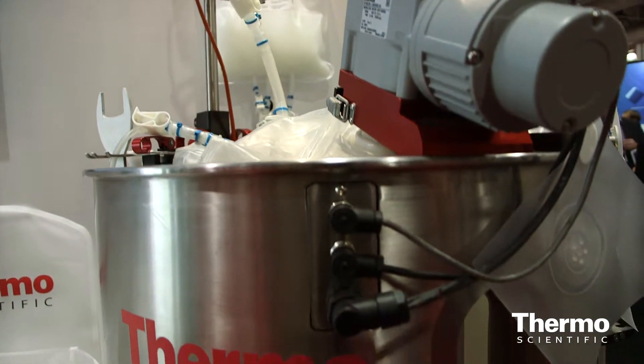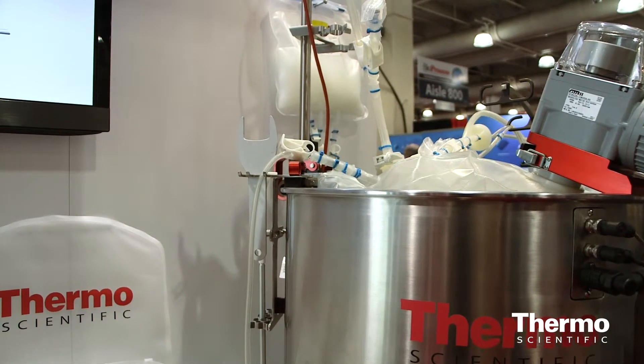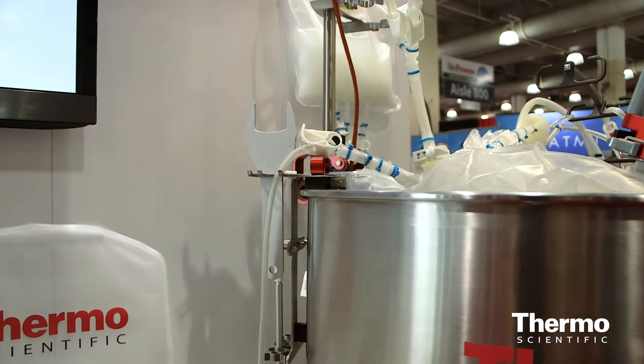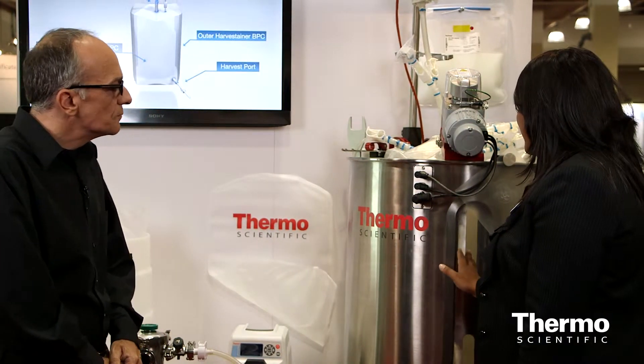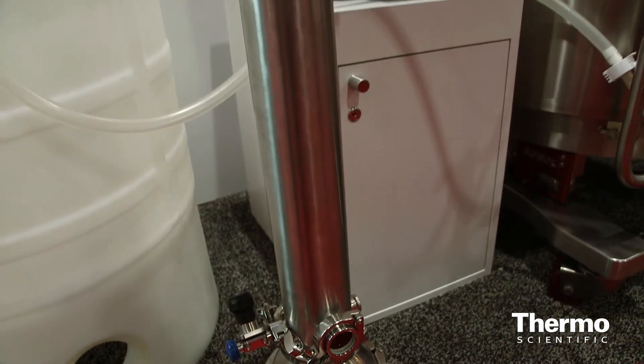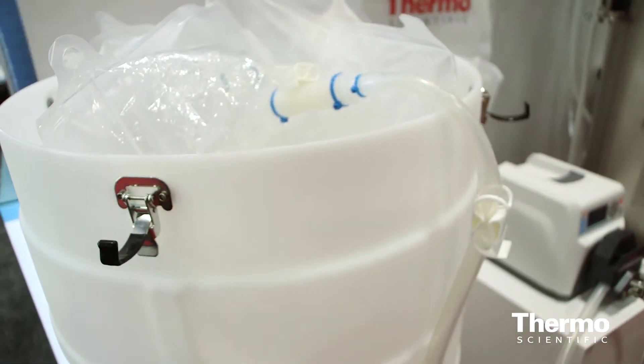The bioreactor here is a stainless steel container. It provides temperature control and a mixing system, and we pair it with other control systems. We offer customers a lot of choice — either open architecture or in turnkey form. We work with single-use sensors; this is the probe area — the sensing technologies for monitoring what's going on in the system. Here you're seeing a perfusion system. Perfusion is a vastly growing technology at the moment. This is a refined ATF perfusion system. We partner with the latest technologies to bring the best to our customers. And here you see a harvest container — this is a Thermo product used for cell harvest, dedicated for vaccine manufacturers and microcarrier cultures.